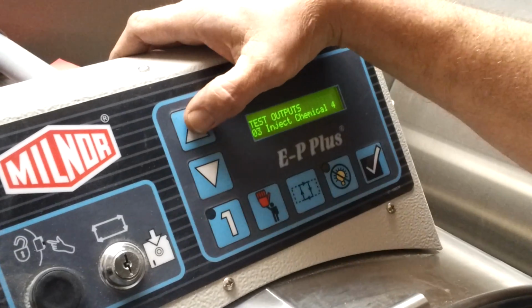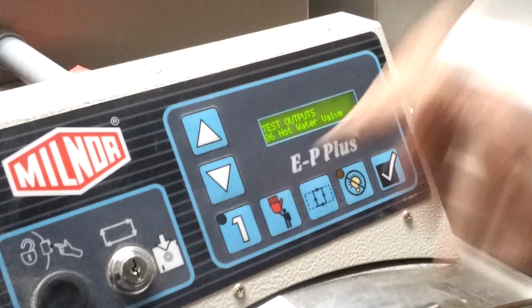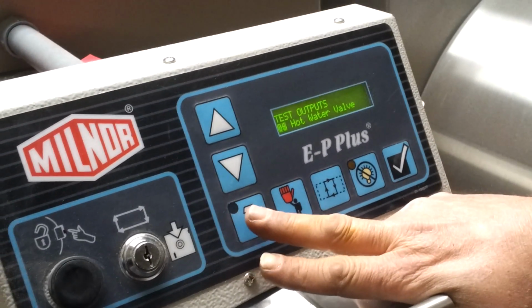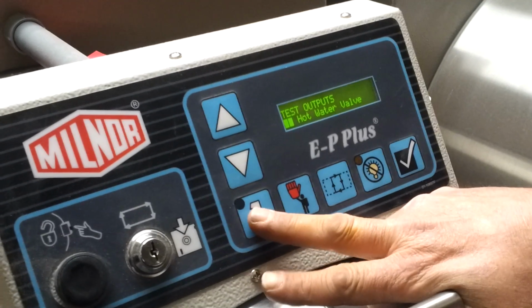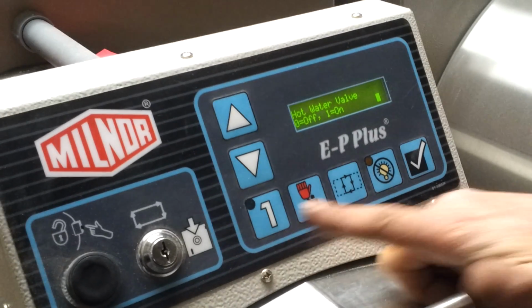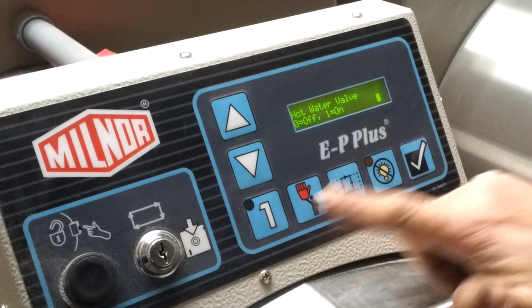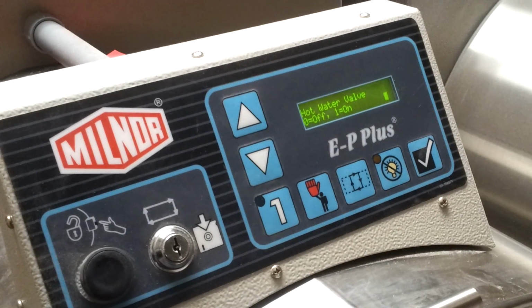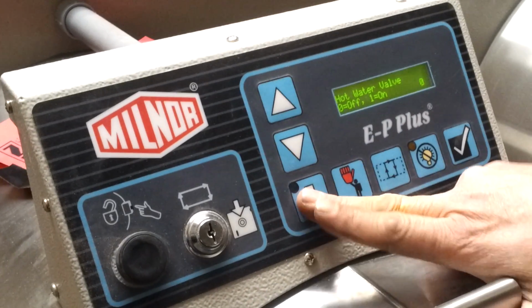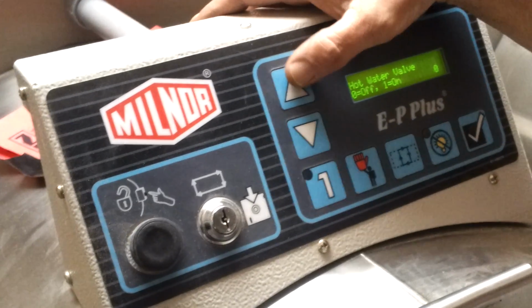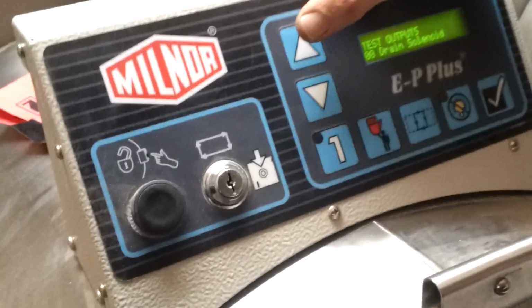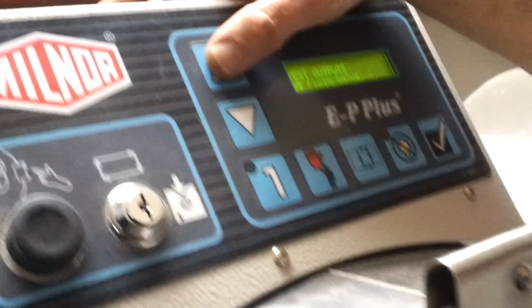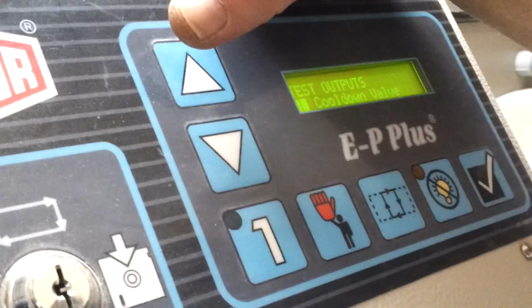Now with a manual menu, you can go in and turn off and on all the components of this machine. In other words, I selected the hot water valve. If you press 1 once, it denotes it off. You press it again, and there's your hot water valve coming in. And you can go through and check your hot water valve, your cold water valve, drain solenoid, flush valve, just about every component of this machine.